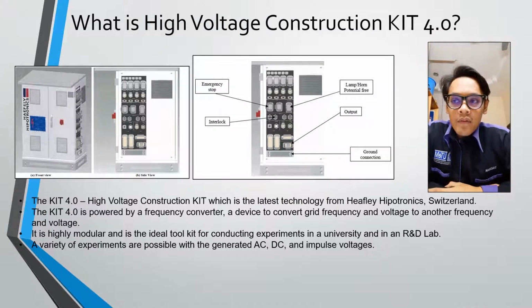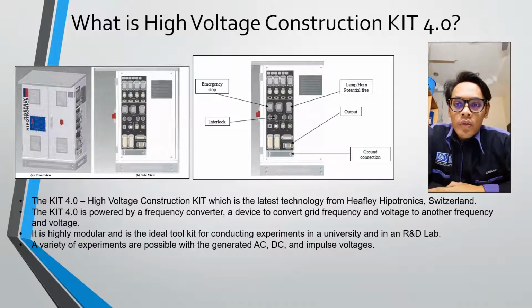What is High Voltage Construction Kit 4.0? The High Voltage Construction Kit 4.0 is a system of components for application in high voltage technology. The system can be divided into 3 sections. The first section is the source, also known as the Kit FC cabinet or frequency converter. The second component is the high voltage transformer, also known as the single-phase AC voltage test transformer or external transformer. And the last component is the add-ons.